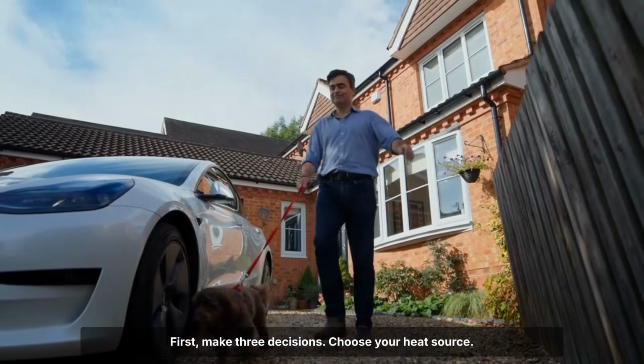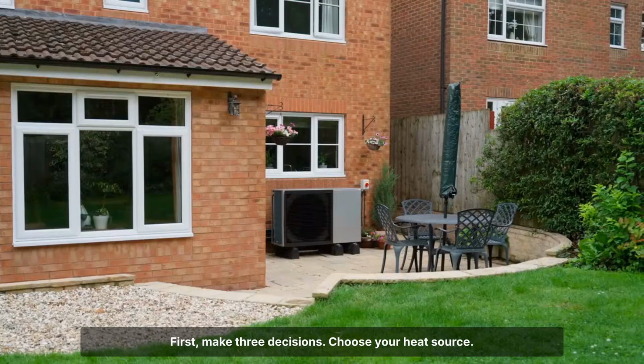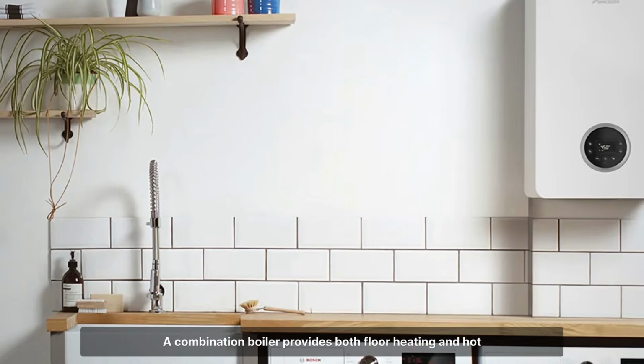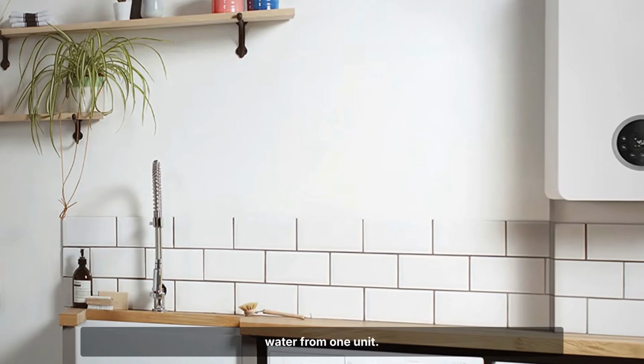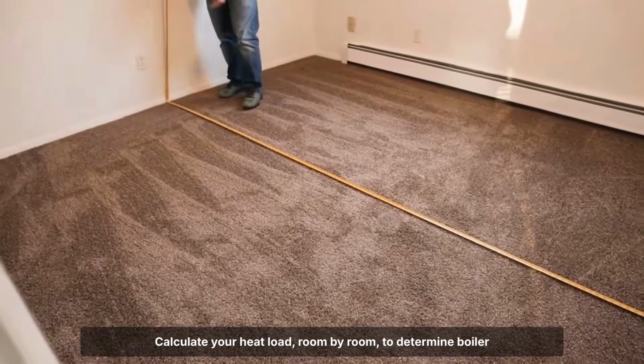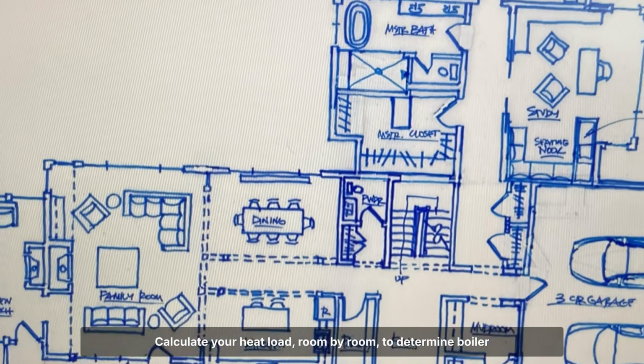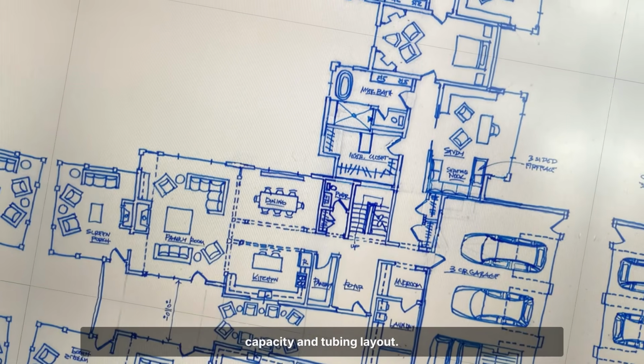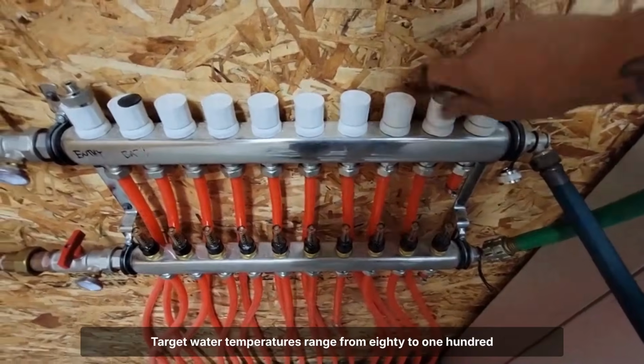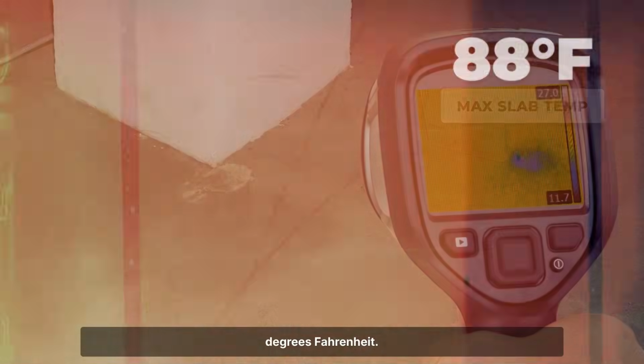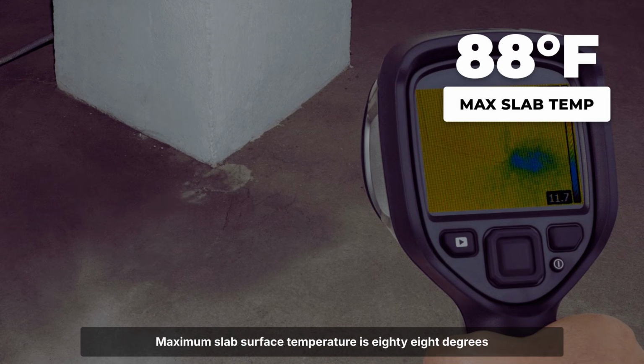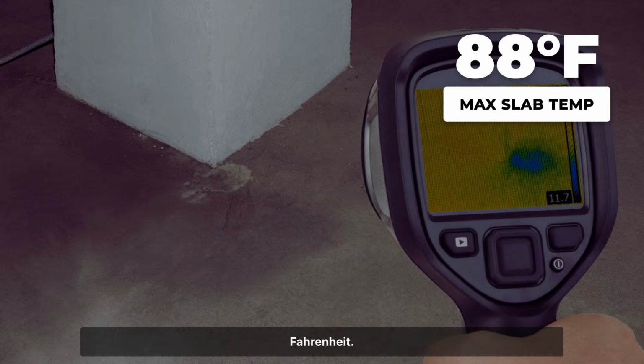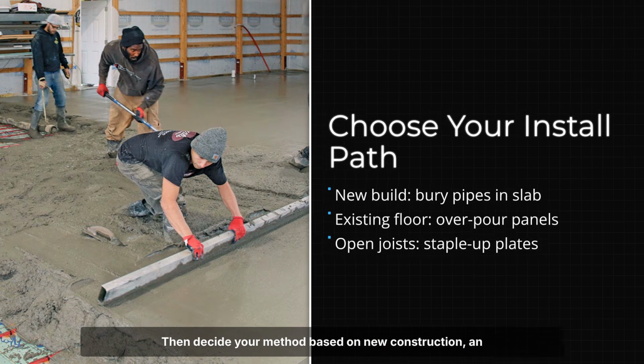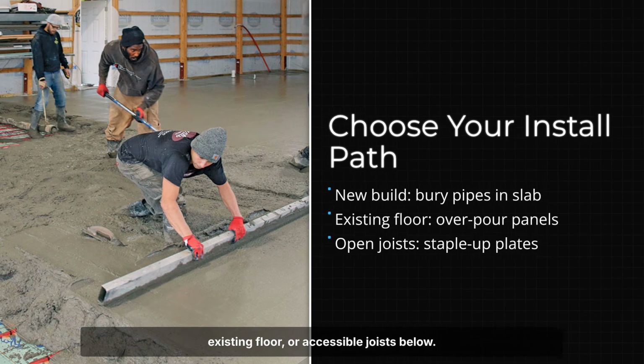First, make 3 decisions. Choose your heat source. A combination boiler provides both floor heating and hot water from one unit. Calculate your heat load, room by room, to determine boiler capacity and tubing layout. Target water temperatures range from 80 to 100 degrees Fahrenheit. Maximum slab surface temperature is 88 degrees Fahrenheit. Then decide your method based on new construction, an existing floor, or accessible joists below.